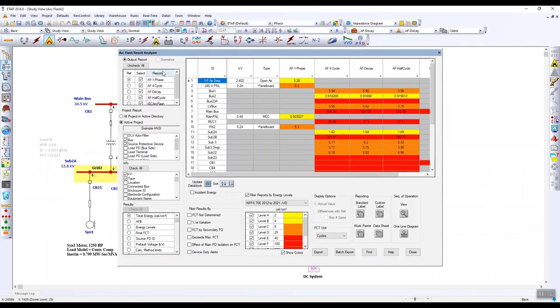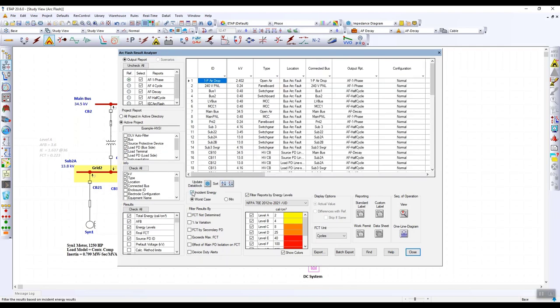Let's take a look at the analyzer. To the left, we see all of the generated output reports based on the various scenarios that were already ran for this project. On the right, we see information for the elements we have selected on the left-hand side. We can include additional devices and information by checking more of the options on the left. If we select the incident energy box and select worst case, this will show the worst case based on the output report. This comes in handy when you're generating the arc flash labels for your project.